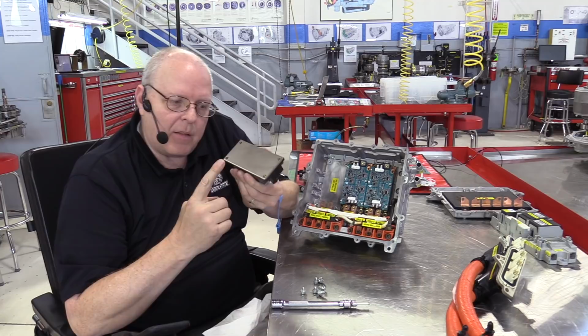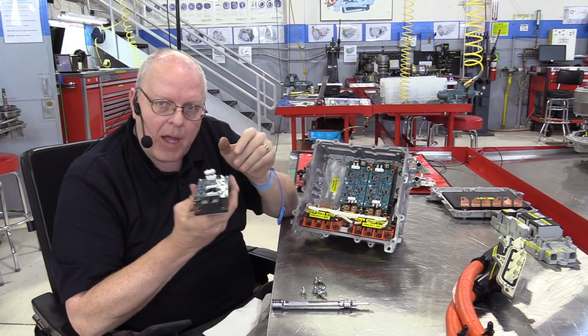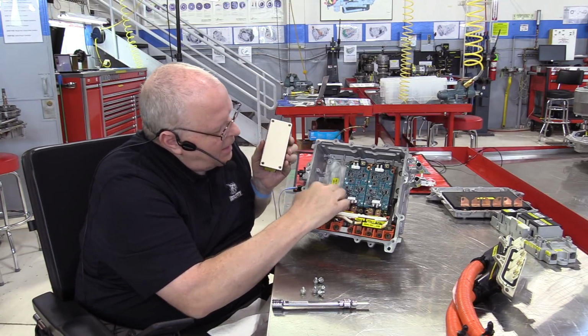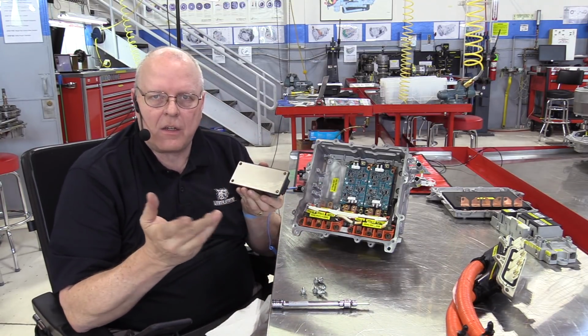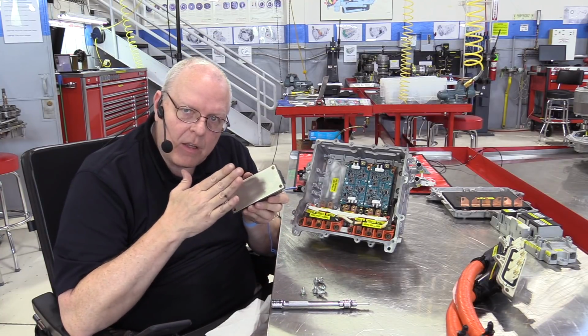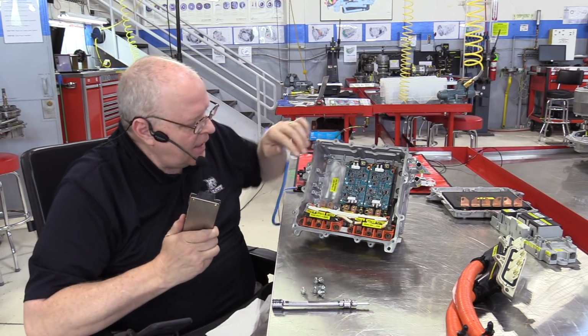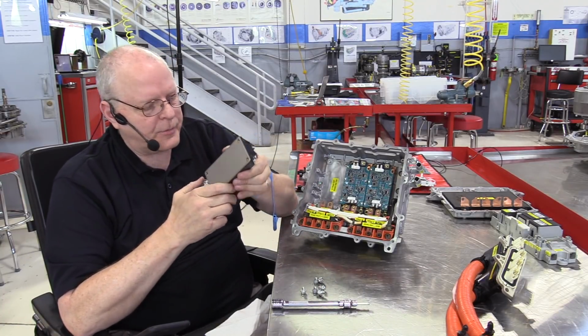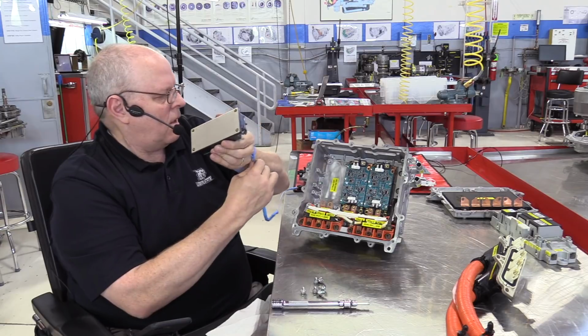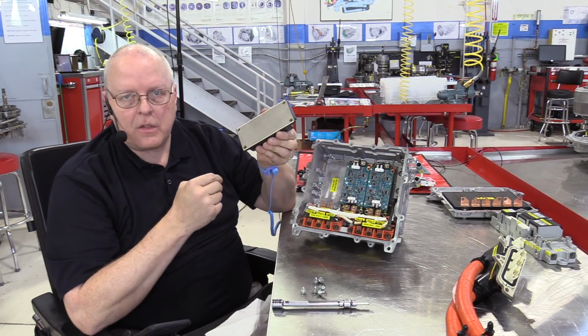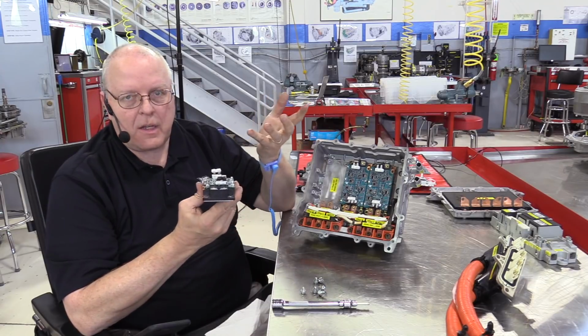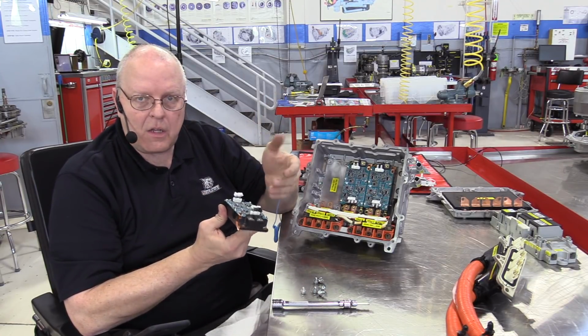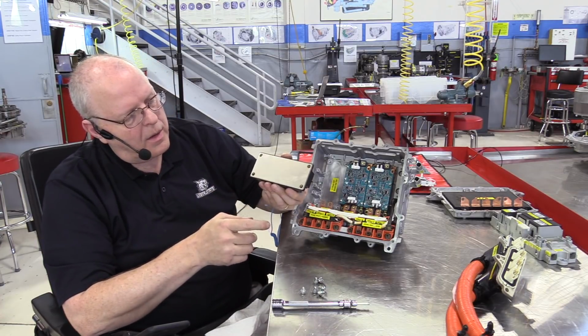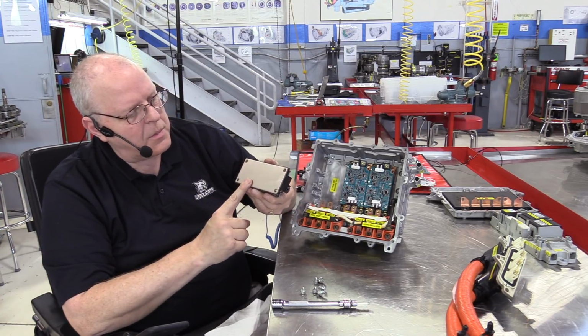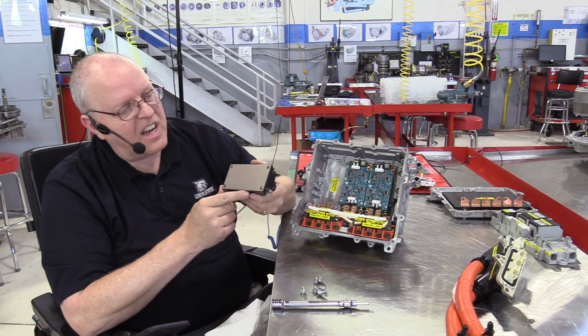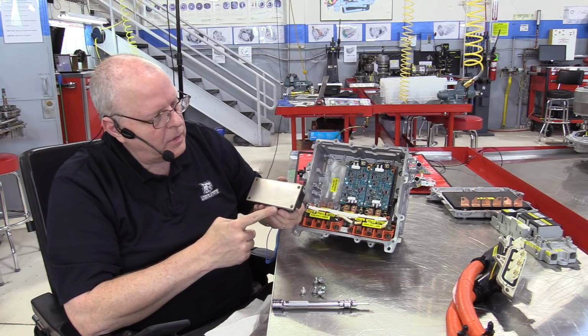Now, I forgot to mention, these flat surfaces here on the back side of these IGBT modules need a heat sink compound, or heat sink grease, as some people call it, to help the transfer of heat out of these components into the housing itself. Oh, by the way, notice I'm wearing an anti-static wrist strap. I have an anti-static mat over there that's grounded to the table, so I don't have an electrostatic discharge from my body to the electronics here. And of course, I'm not touching them anyway, but you should always wear a wrist strap for something like this, connected to your table or bench, toolbox.